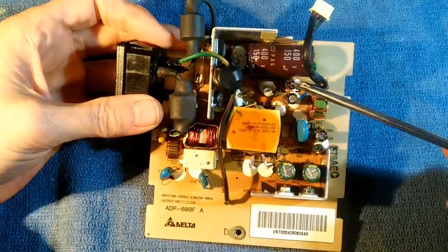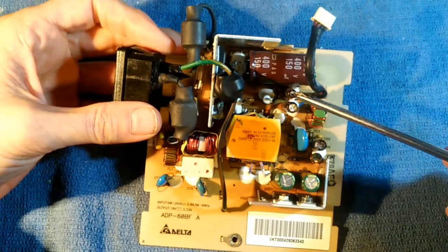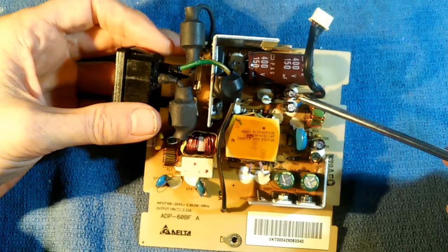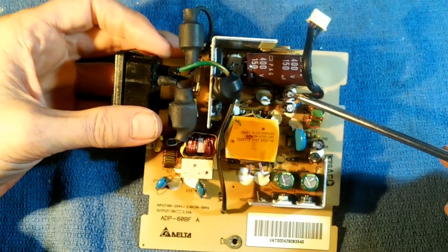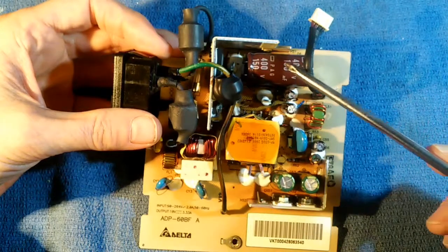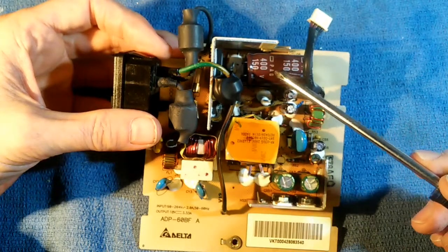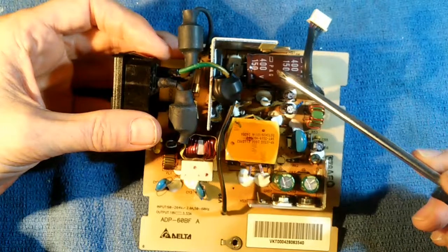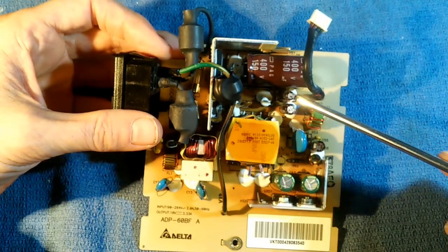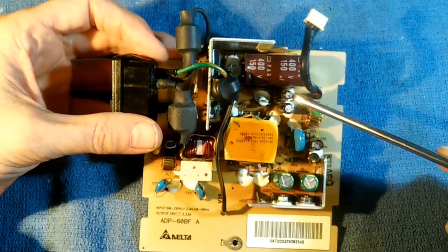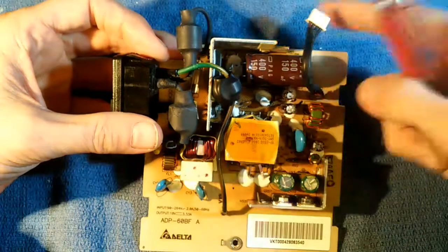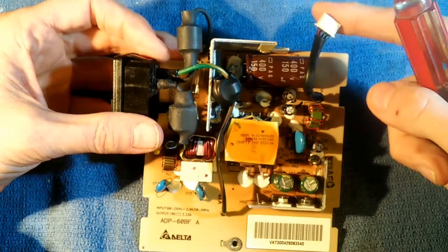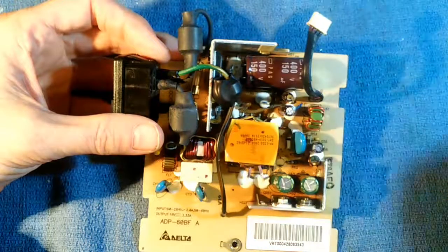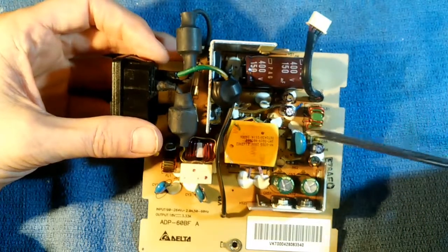We also know that this little capacitor here, C5, this little tiny 22 microfarad cap, can fail with pretty high frequency. The failure may be related to excessive heat being put out when this capacitor is dying. Now, if this capacitor goes bad, you're going to see an abnormally low voltage on the output, but the voltage will be steady. There won't be a sawtooth waveform, it'll just be a flat voltage.